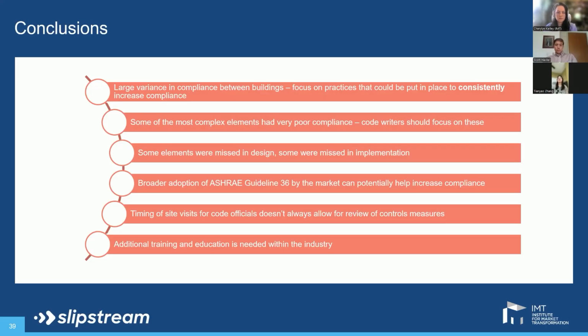We also recommend broader adoption of ASHRAE Guideline 36 by the market as a whole, which can help address some of the controls issues we're seeing. Guideline 36 was created to develop and maintain best-in-class standardized HVAC control sequences. If we had a BAS package pre-programmed to meet Guideline 36, with controls contractors also trained on it, that could reduce the amount of time engineers and contractors spend programming and commissioning systems.